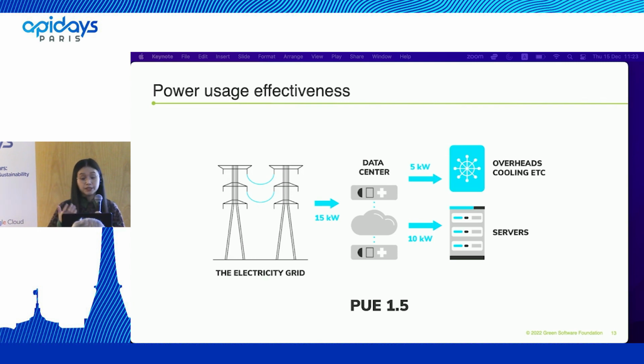Specifically, PUE tells us how much energy coming from the grid goes to the server itself, and how much goes to cooling and other overhead activities. When a data center's PUE is 1, that means for every kilowatt hour of energy that comes in, all of it goes to do something useful, supporting our applications. But when PUE increases to 2, that means for every 2 kilowatt hours of electricity that comes in, one is used for computing and the other is used for overhead activities.